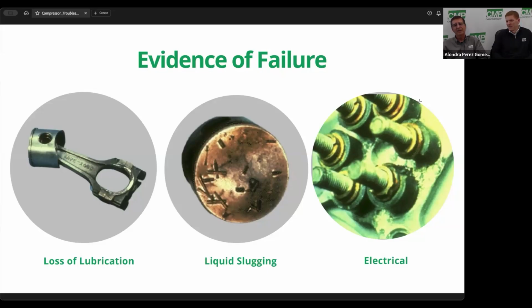Out of the 90%, I would say at least 70% of all compressors fail because liquid enters the compressor. Zero superheat, whether it be on startup or whether it be just where the coil ices up, or it floods back in there and thins the oil out where it can't lubricate, and you don't have an oil safety switch on it or one that's working. But 60 or 70% fail because liquid enters the compressor. So we've got to stop that.